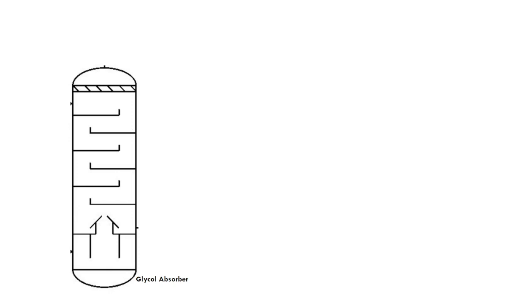The water is removed from the gas using water-absorbing material known as glycol. Lean glycol is glycol which contains no water. The heat exchanger is used to cool the glycol to increase the absorption efficiency.